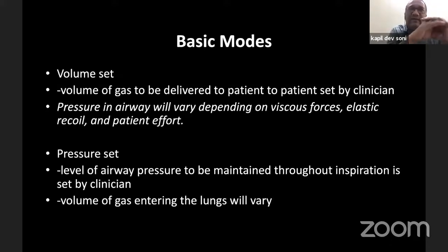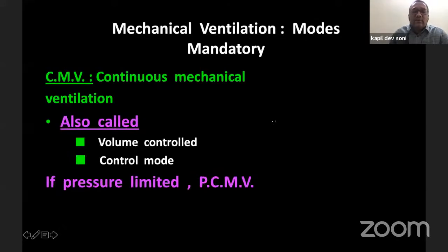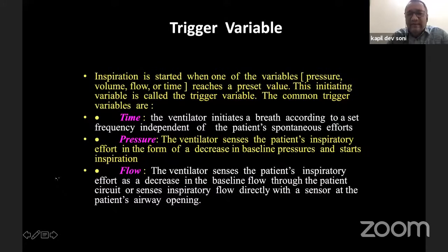Whereas in a pressure controlled mode, the amount of pressure which can be applied to the lung is fixed, whereas the volume, flow, and time can vary based on the lung characteristics, the compliance and resistance of the lung. So a control mode or a continuous mechanical or a mandatory mode is basically when the patient is completely paralyzed, during OR or during the initial phase of intubation. What the machine delivers is basically a continuous or controlled mode. So this trigger could be a pressure trigger, it could be a flow trigger. In certain machines, it could be a time trigger. In a pressure trigger, the machine senses a drop in the pressure within the circuit and is triggered to give a breath. Whereas in a flow trigger, the machine senses a reduction of flow in the circuit and starts giving a positive pressure breath. So that is just the mechanism of how the triggering happens.